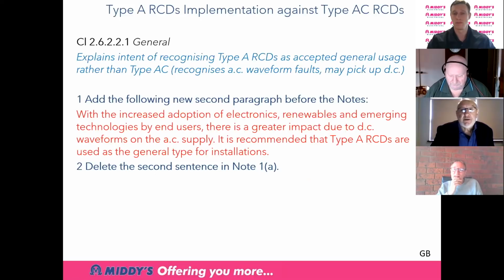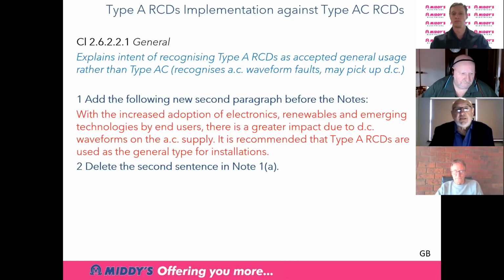Hi, this is me, Gary Busbridge here, and same thing. It's good to be able to get some information out to the industry on this Amendment 2. One of the most important things we've got to consider is nowadays we have a lot of DC waveform in the system in regard to solar. You've got your solar systems, you've got electronic fridges, you've got your TVs, and all of these have got a DC component in there. And what we found is that the general type of RCD that we are recommending at the moment is a type AC, and that type AC is really only reliable on AC waveform faults, and it may pick up DC, but it may not.